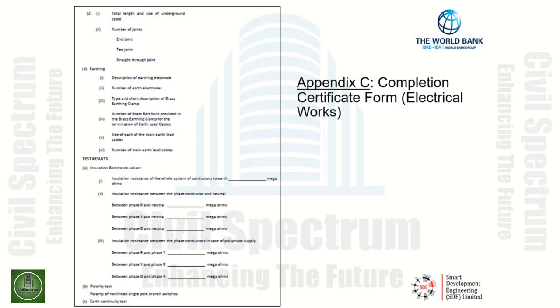As you will see here, the old existing color code is indicated with respect to the colors of phases. This is the old existing IEE standard. A note to the code user with respect to the completion form here, any new installations would need to be changed to the new color code indicated in the IEC standard.